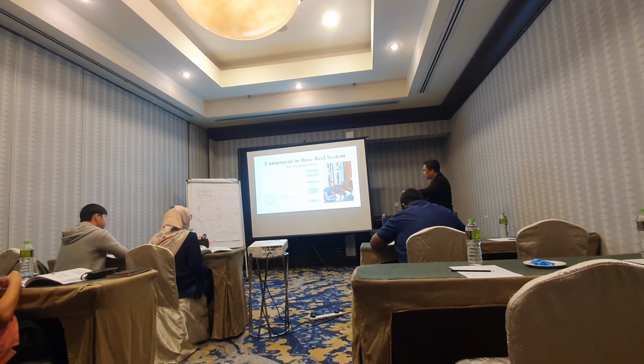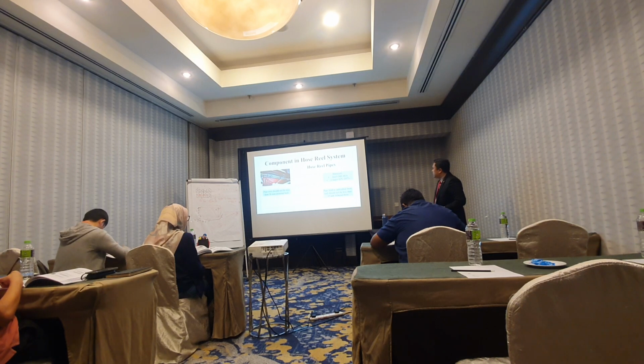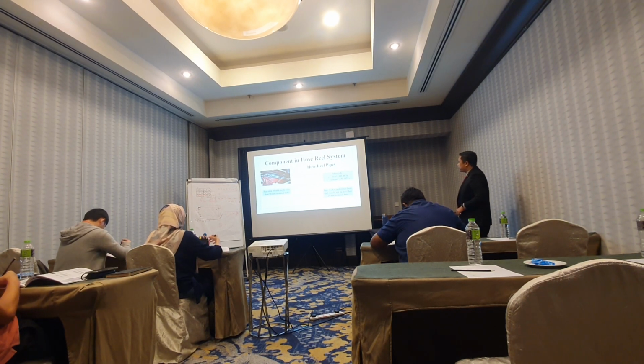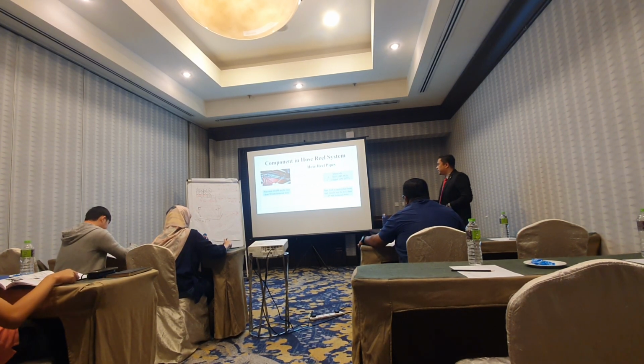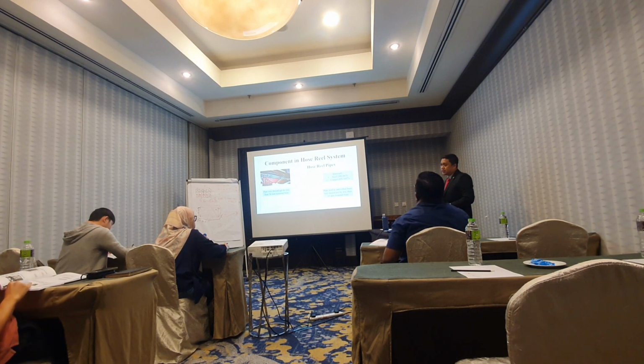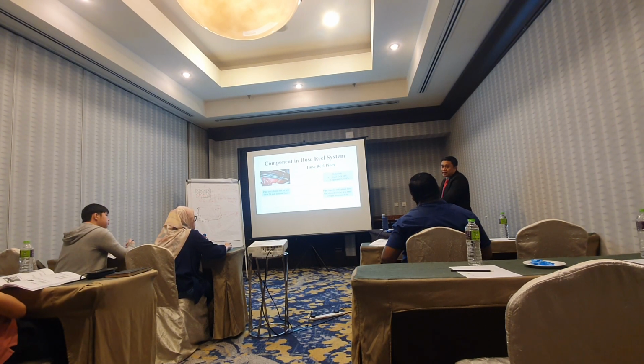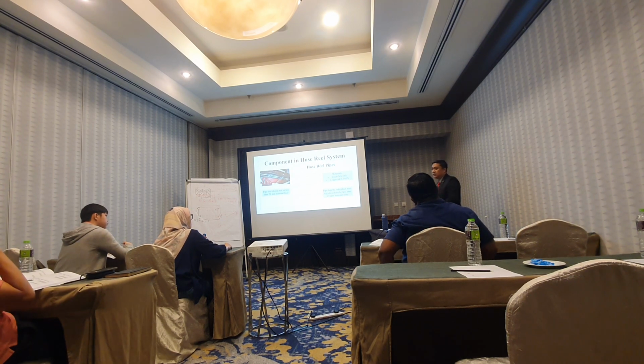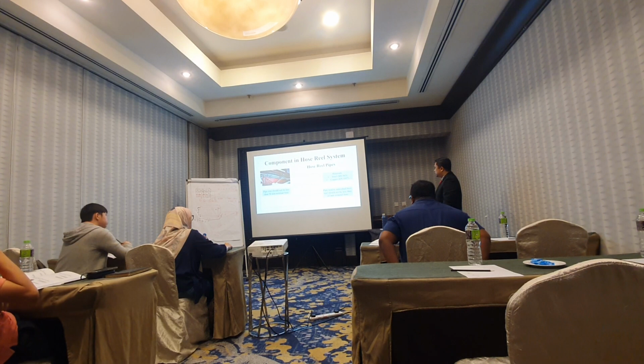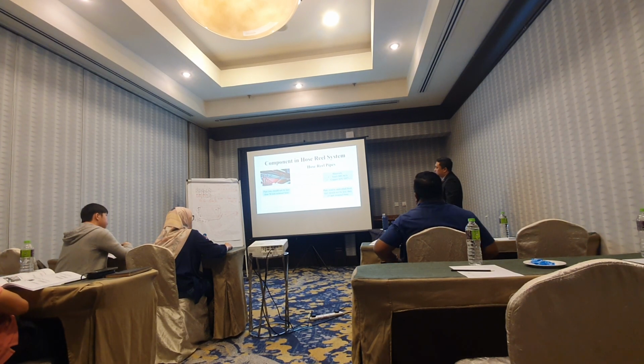Okay, component hose reel, and then we have a hose reel pipes. Hose reel pipe kalau dekat luar black pipe pun boleh pakai lah. Tapi kalau project government, they will allow you to use a black pipe. The minimum is GI class C. That is the minimum. So you will have a differ in the price lah. Yet it is still allowable to use the steel pipe lah. Steel pipe, black steel boleh.